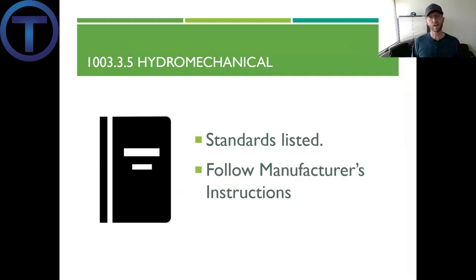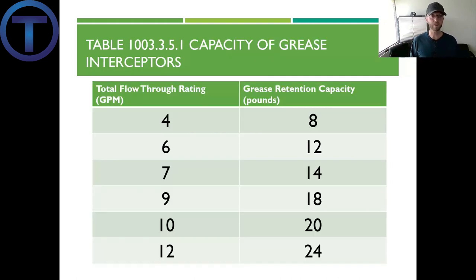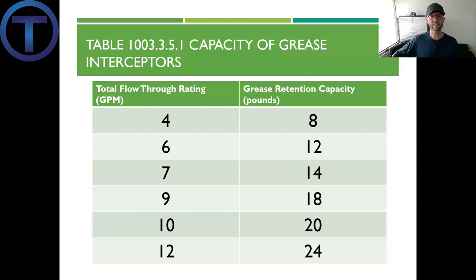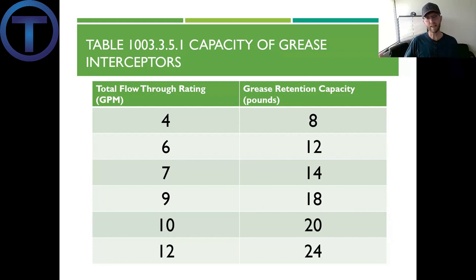Section 1003.3.5 talks about hydromechanical systems, listing standards they need to meet and stating we follow the manufacturer's installation instructions. For sizing a grease interceptor, there's a specific relationship demonstrated in Table 1003.3.5.1, which covers the capacity of grease interceptors. On the left is the total flow-through rate — the amount of fluid expected to be processed — and then there's the grease retention capacity. There's a two-to-one ratio: for every gallon per minute, there's a two-pound expectation on grease retention, so four gallons per minute should retain eight pounds, and so forth.